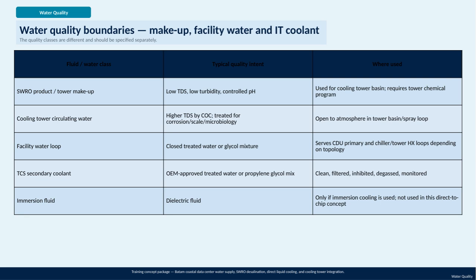For the facility water loop, we typically use a closed system with treated water or a glycol mixture, depending on the topology. This loop supports the primary cooling distribution unit and chiller or tower heat exchanger loops, maintaining efficient heat exchange while preventing contamination. The TCS secondary coolant must be an OEM-approved treated water or propylene glycol mixture. It's clean, filtered, inhibited, degassed, and constantly monitored to ensure optimal performance and protection of the system components. Finally, immersion fluids, which are dielectric fluids, are only necessary if immersion cooling is used. They are not part of this direct-to-chip cooling concept, so they're not relevant here.